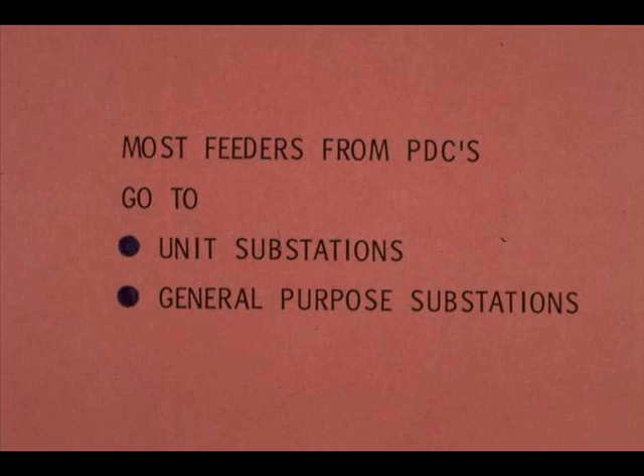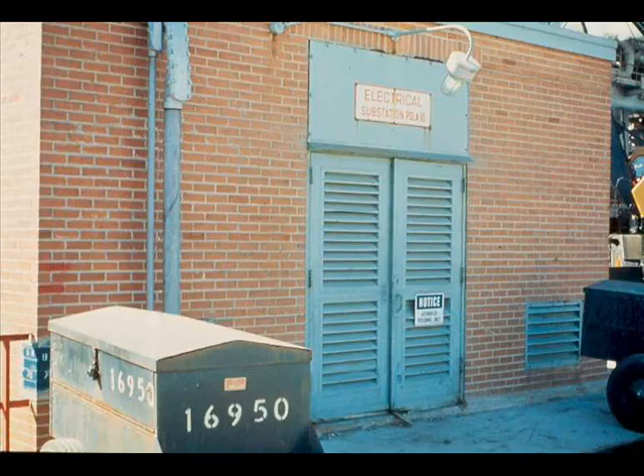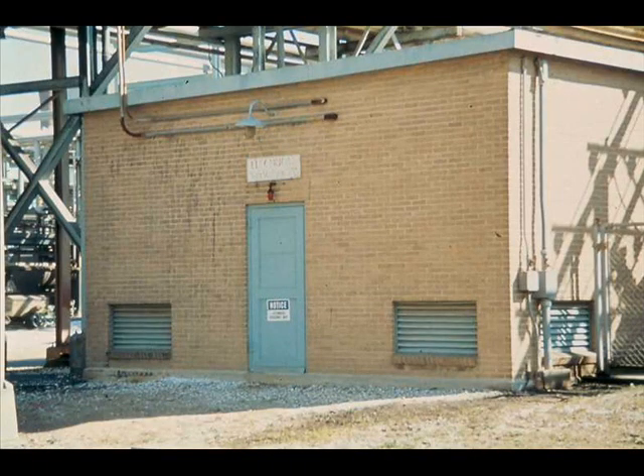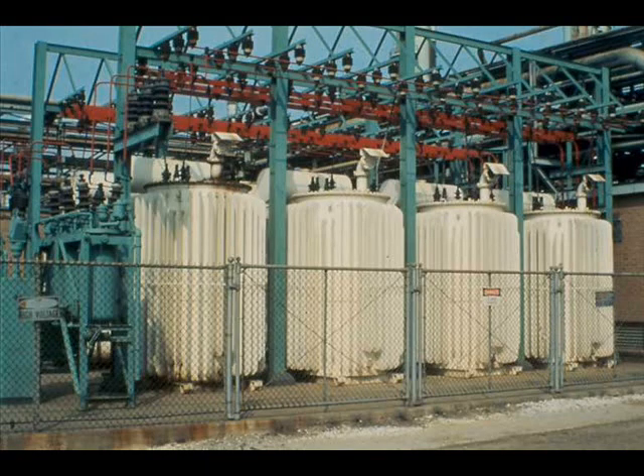Most feeders from PDCs go to substations, which one large plant classifies as unit substations or general purpose substations. A unit substation serves a single process unit — for example, PSLA-10 substation serves number 10 pipe still. A general purpose substation is not limited to serving a single unit; one such substation is S-10, named because it is on Avenue S and 10th Street. At substations, transformers step down 13,800 volt current to 2,400 volts, 480 volts, 240 volts, 120 volts, or other required voltages.